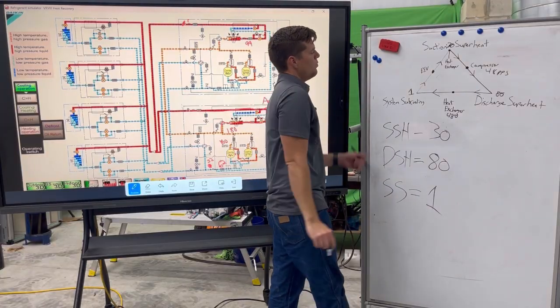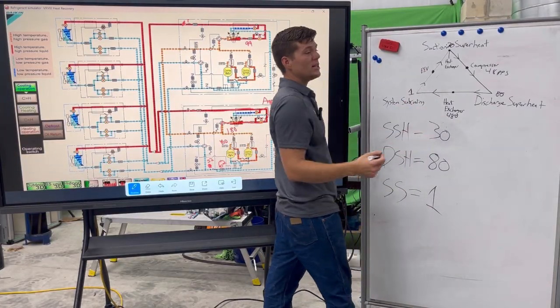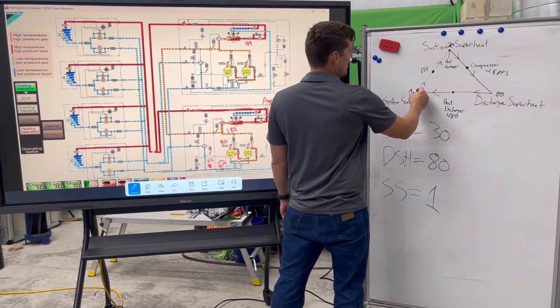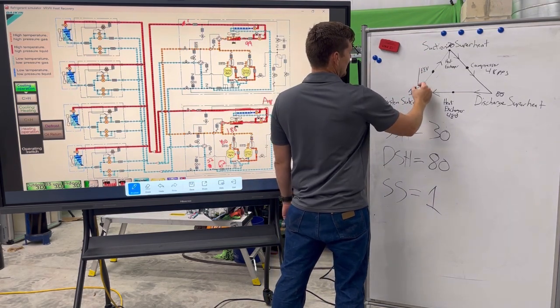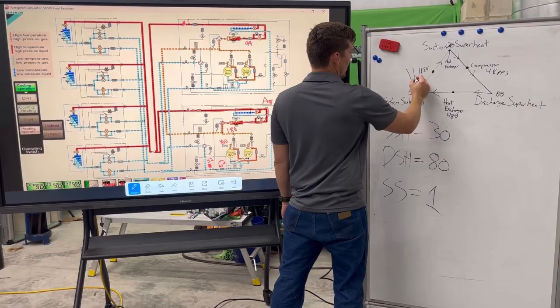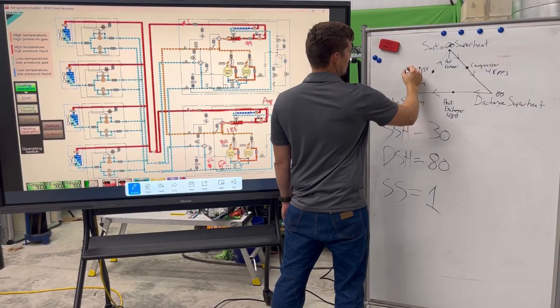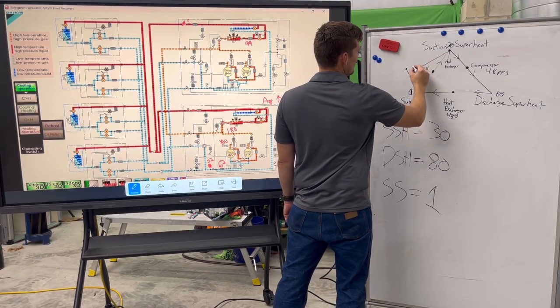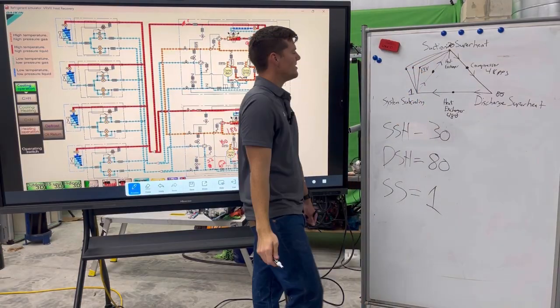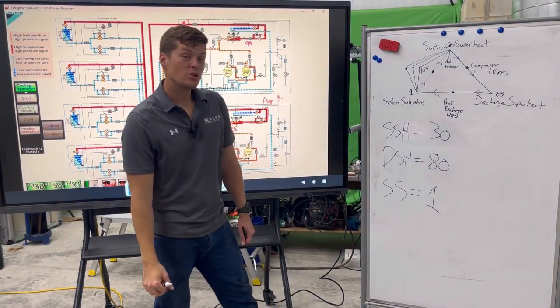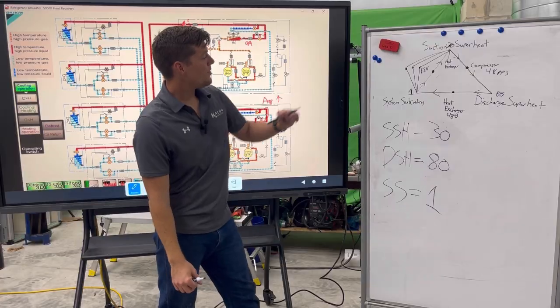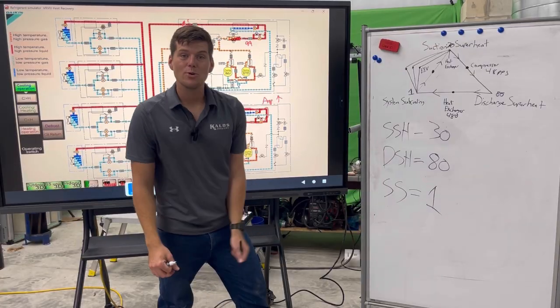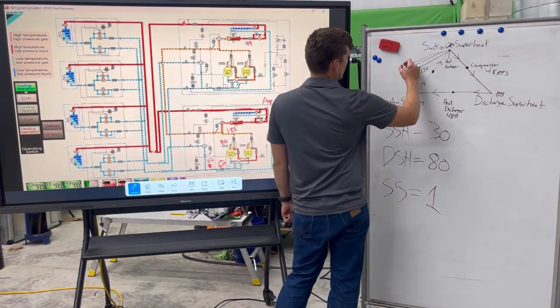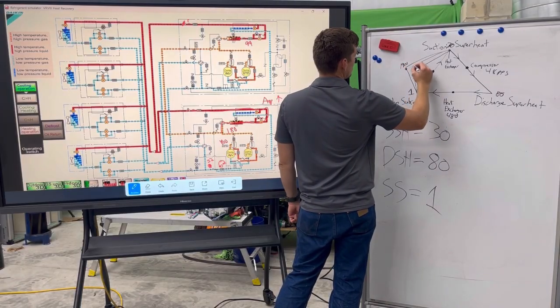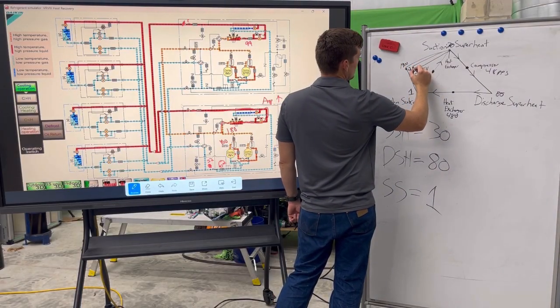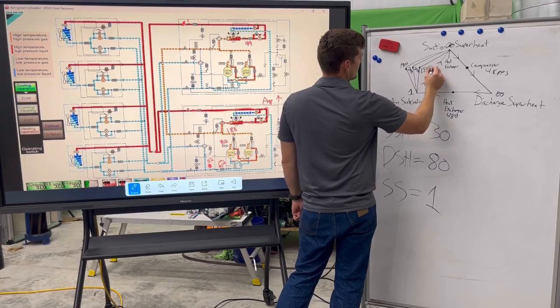Let's keep moving. Where are we going to go next? Well, we're going to go to EEV. Unfortunately, with VRF, this triangle gets a little bit messy. The messiness is that there isn't just one electronic expansion valve. Let's say there are 4 indoor units. Doesn't look like a triangle much anymore, does it? So I'm going to go through and plot all my indoor expansion valves. What are my indoor expansion valves at? This one's at 1900 pulses. This one's at 2000 pulses. This one's at 2000 pulses. And this one's at 800 pulses.